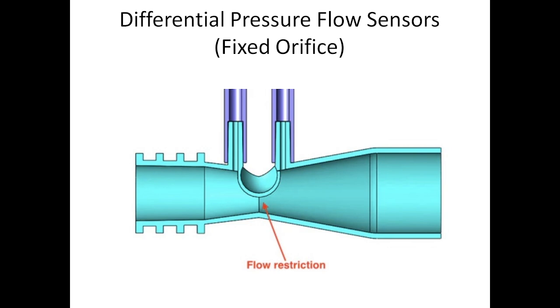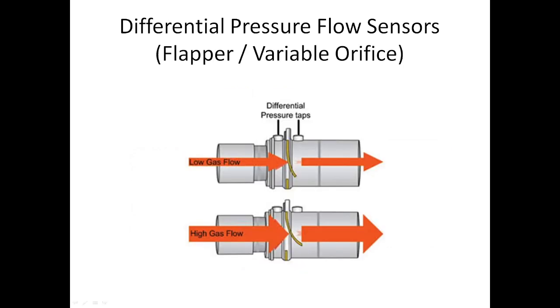One consistent flow rate, no problem. Now on these ones here, the variable flow rates, you could have a low flow for, let's say, a pediatric patient, or you could have a high flow. Now what it's going to do is it's going to come through and it's going to lift the flapper just so, and that creates a little gap down here. So a low flow, the flapper comes down and it's almost closed, so it still creates quite a bit of difference on one side or the other. And as the flow rate increases, the flapper is going to lift and it's still going to maintain that difference of pressure from one side to the other. So that would be a variable orifice or flapper style flow sensor.